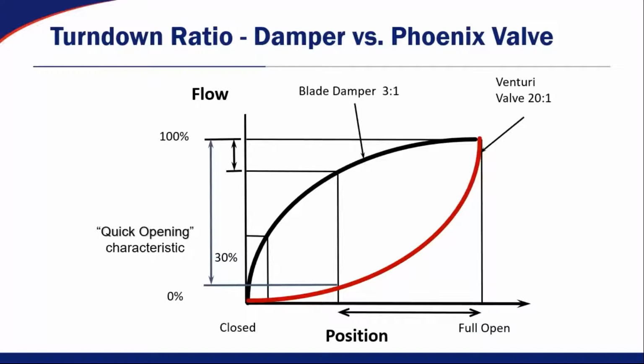So once you take the pressure out of the equation, we can get very finite measurement across the entire flow range of that valve when we're calibrating it, so that when it gets out in the field, you get that 20-to-1 turndown ratio, which is useful not only in rebalancing buildings in the future, but also giving you the flexibility of turn down at night and running it full time in the daytime to make sure that you still have the ventilation rates required.